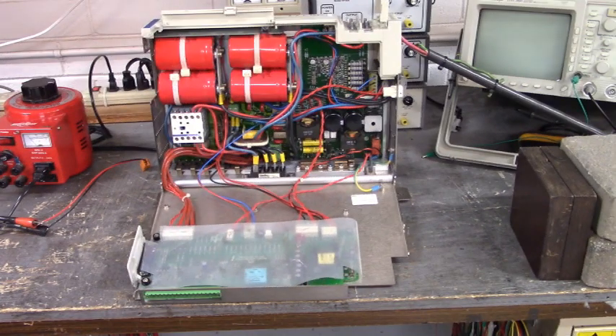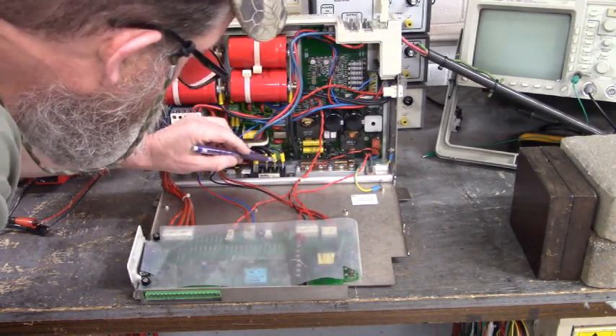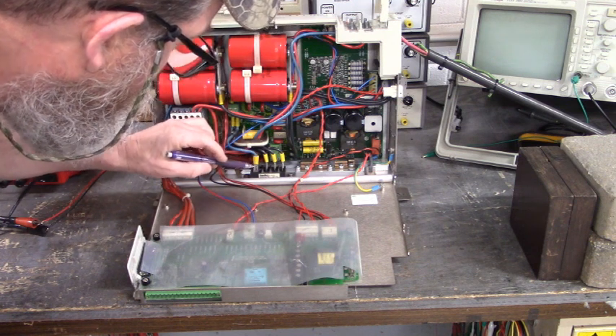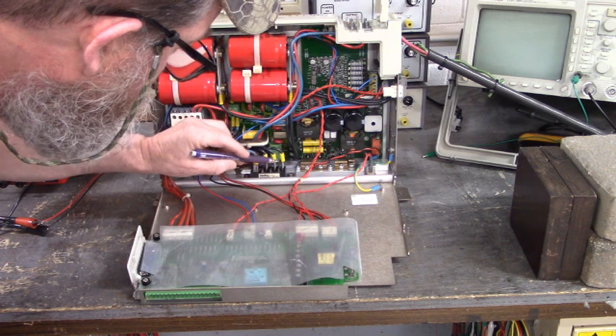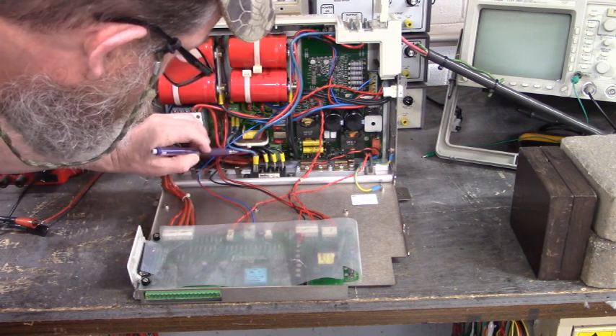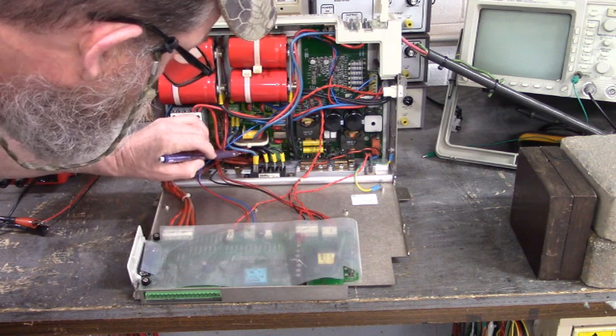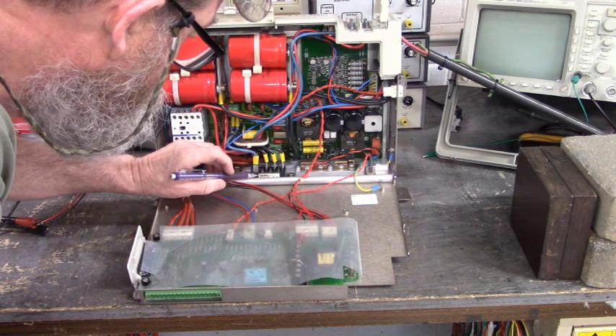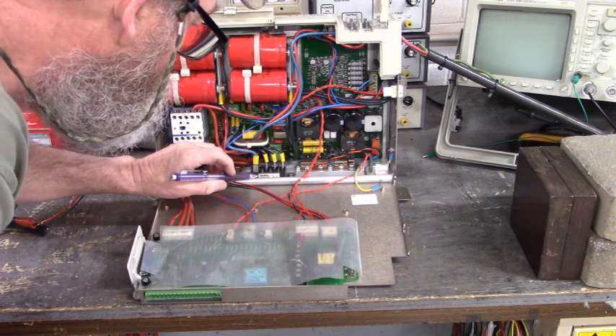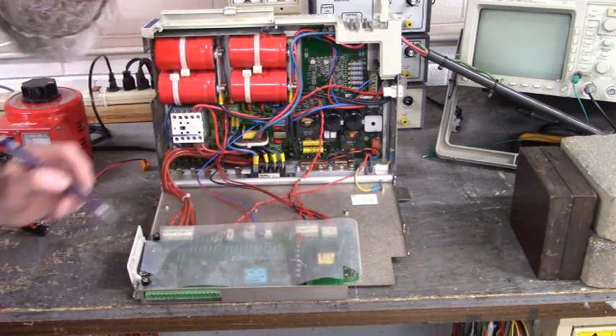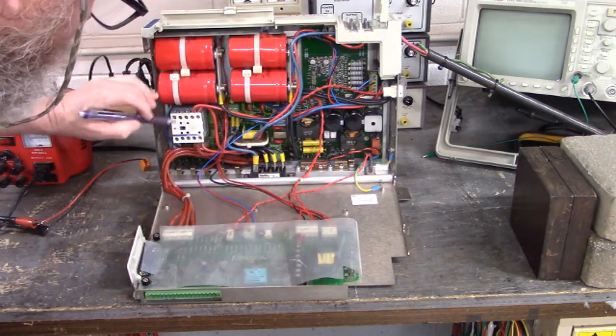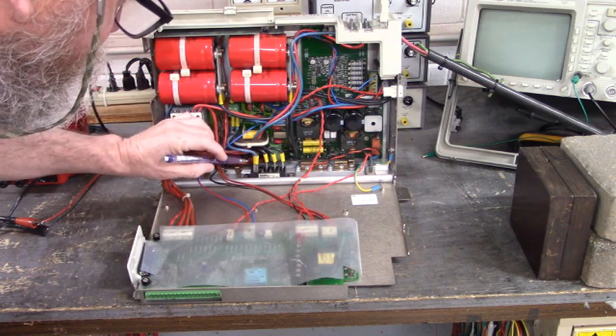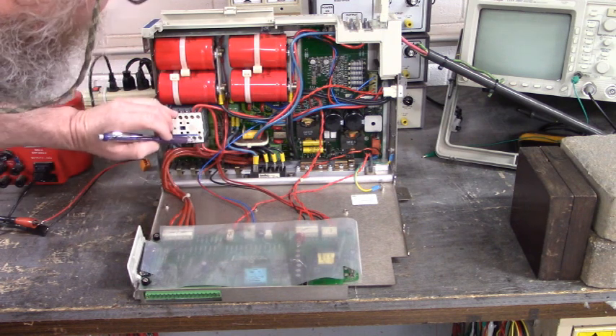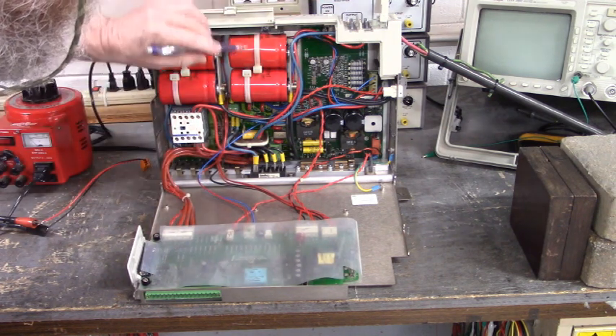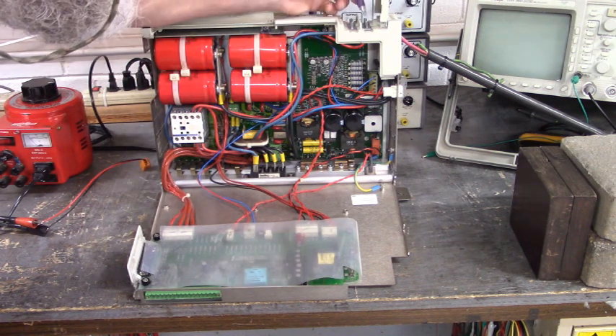Let's take a look at what's inside. Now right down here is your three-phase bridge rectifier. Here's your L1, L2, and L3 line coming in. Here's your bus ground, the blue wire, bus plus is the red wire, and this part is manufactured by Sanrex, part number DF30CA160. Over here is the contactor that routes the DC from the three-phase bridge rectifier out to these terminals and bus capacitors. Now up here is bus plus and here is bus ground.